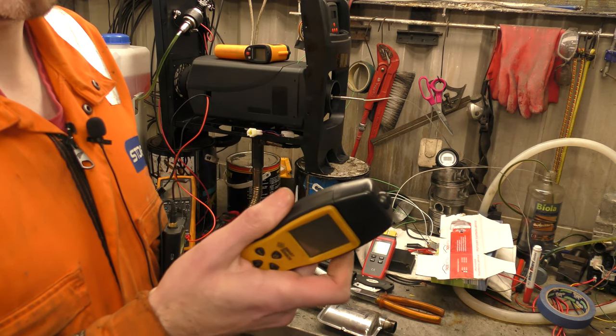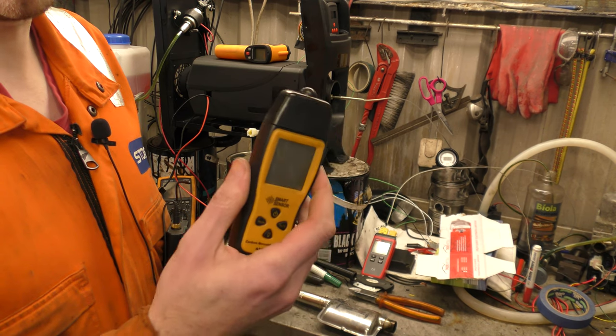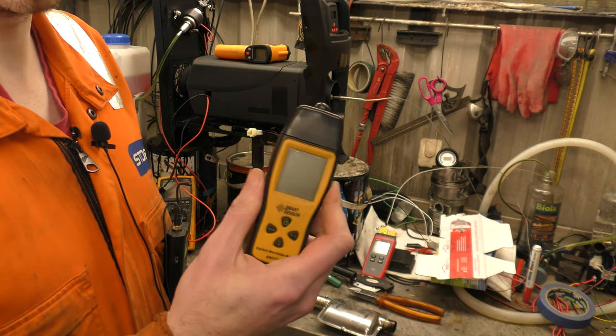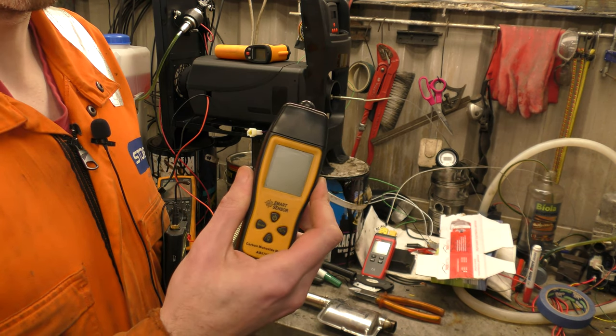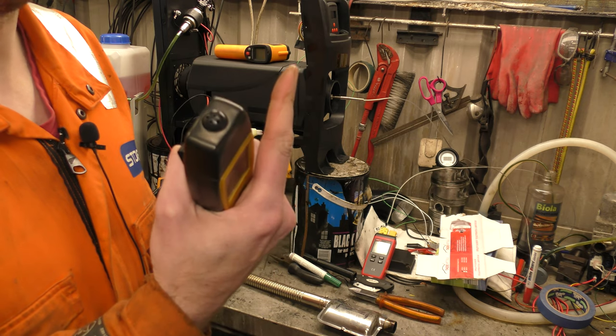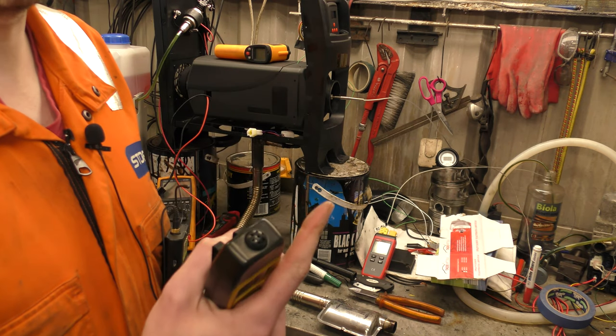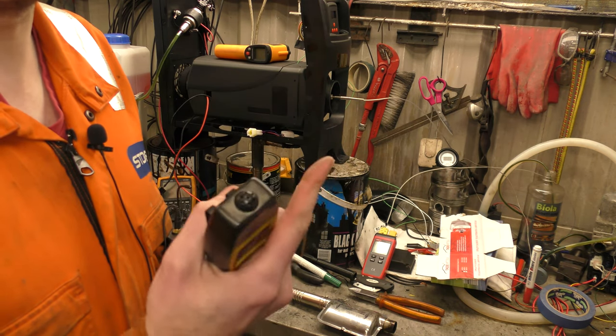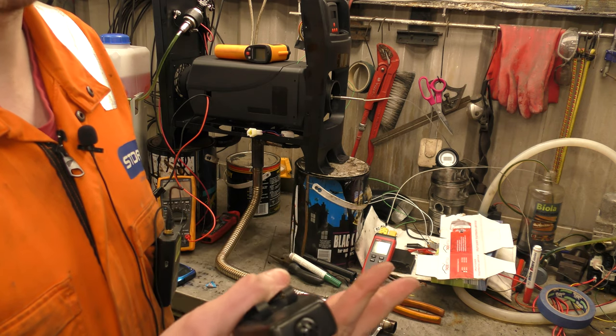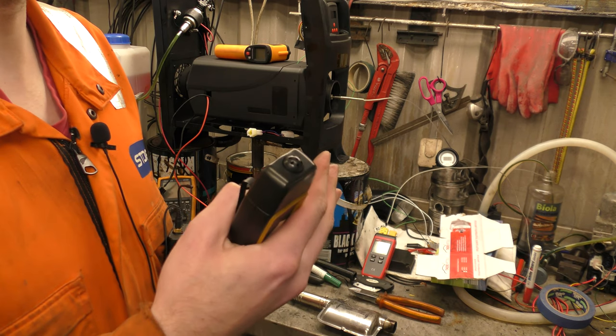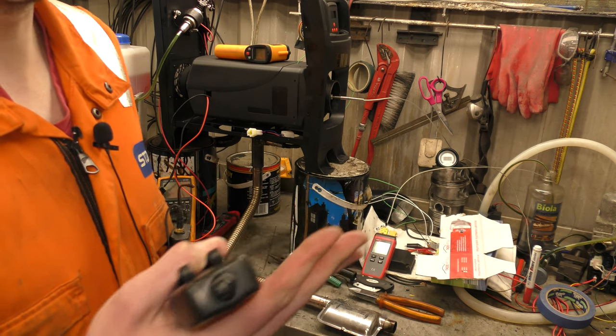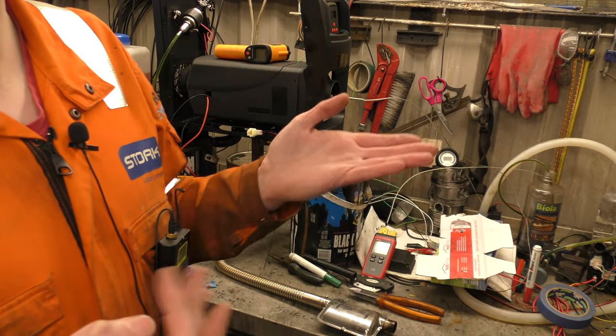Also, bear in mind that if you're getting a high carbon monoxide reading, you might actually have to turn the fuel up, not just down, because you might find that you've not got enough fuel to make it hot enough inside for it to atomize and burn properly. So, you'll have to just experiment basically.